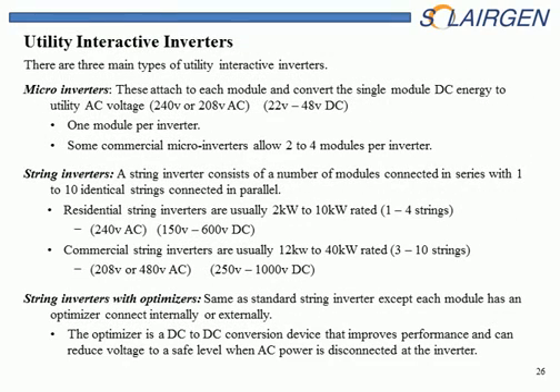Let's look at the three different types of utility interactive inverters that we'll typically see on our residential install or commercial install. The microinverter, which is matched 1-to-1 to a module, so the individual module DC voltage will never be more than 22 to 48 volts, so it's a safe voltage. And when the utility shuts down, the AC shuts down and shuts down all production. So that's a safe installation.